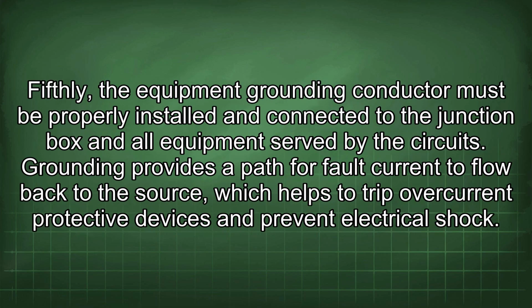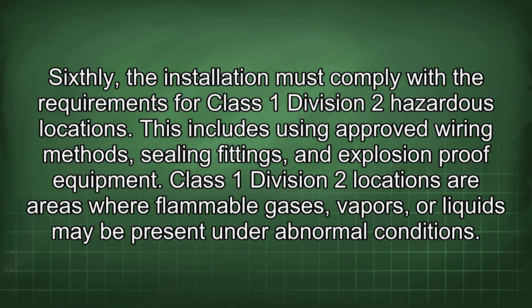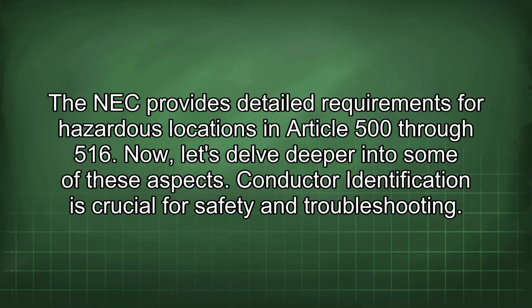Fifthly, the equipment grounding conductor must be properly installed and connected to the junction box and all equipment served by the circuit. Grounding provides a path for fault current to flow back to the source, which helps to trip overcurrent protective devices and prevent electrical shock. Sixthly, the installation must comply with the requirements for Class 1 Division 2 hazardous locations. This includes using approved wiring methods, sealing fittings, and explosion-proof equipment. Class 1 Division 2 locations are areas where flammable gases, vapors, or liquids may be present under abnormal conditions. The NEC provides detailed requirements for hazardous locations in Articles 500 through 516.